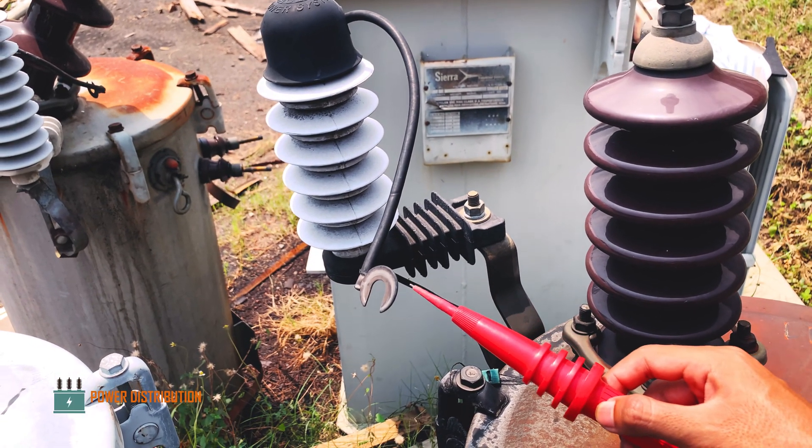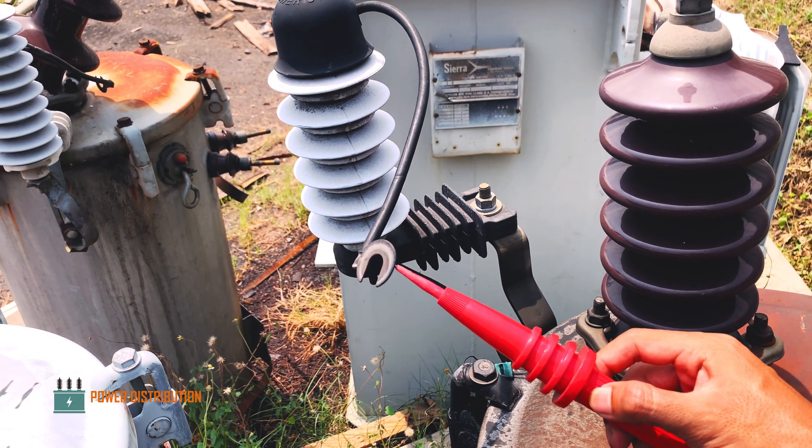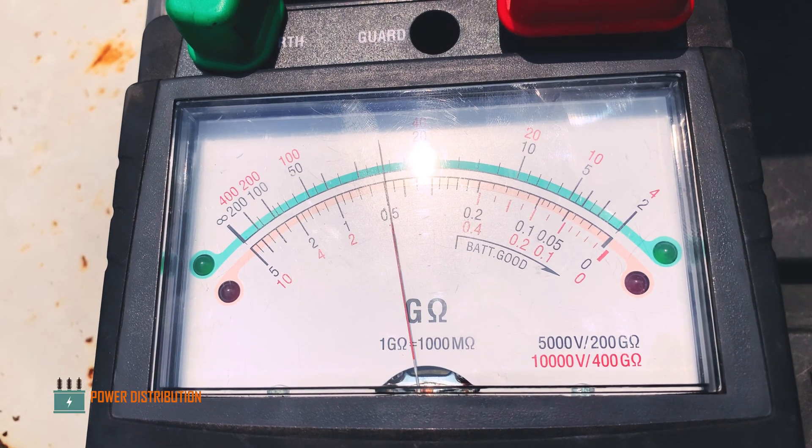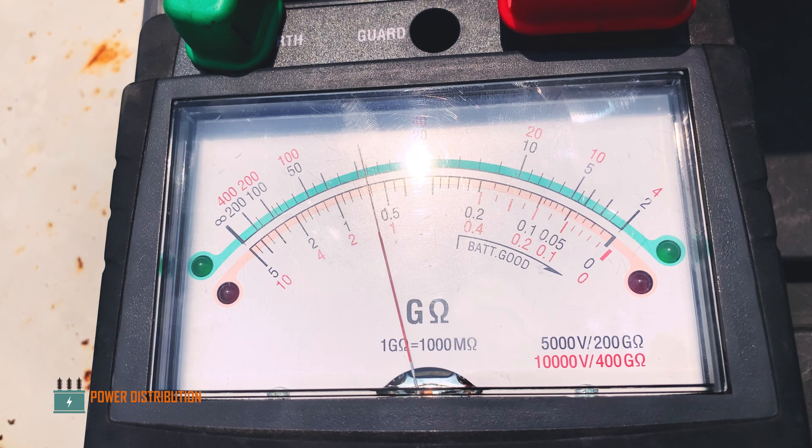In addition, we measure the resistance of the arrestors. As you can see, it shows some reading with a green light, which means the arrestor is intact.